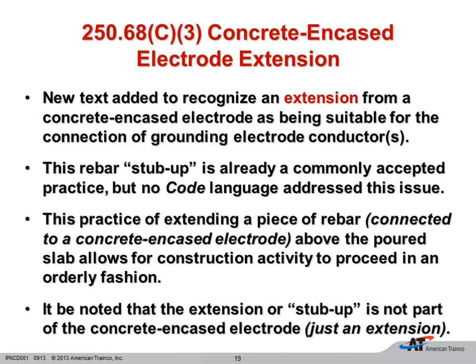In Article 250, they've had some changes. So, of course, this is our grounding and bonding article, and this is one of our 8 choices for grounding electrode. And so in 250.52, it would show us those 8 choices. We would have our water pipe, building steel, and then our third choice would be a concrete encased electrode. Typically, that's our rebar. And so what's happening in the construction field is when they come and pour the foundation, those people understand that the rebar is being used as one of our grounding electrodes. So now they've been stubbing it up. It's been common practice to stub it up, so we have access to that after they poured the slab.